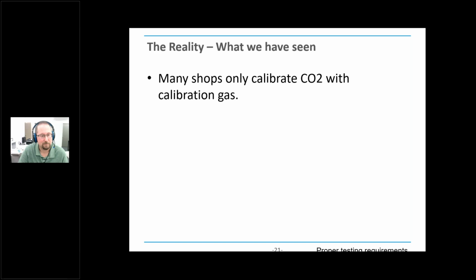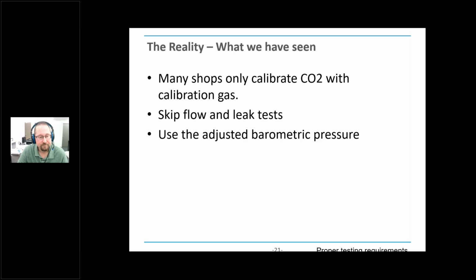As we went out, we talked to people, and what we found was many shops only calibrate CO2 with calibration gas. They might breathe into it, and that's about all they do, which shocked us because of the risk that they're incurring when not doing the testing properly. They often skip the flow and leak test. That's very common. That's why I was happy to hear that 75% of you are doing leak testing. They, like I said, use that adjusted barometric pressure, or they don't have the right equipment, usually specifically flow meters. They're using the wrong kind of flow meter, or the wrong range flow meter, essentially.